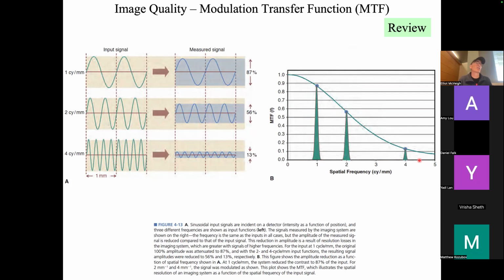You can take that home and compare two scanners: which one's better? You get that 10% value and compare it, and if it goes farther out, that scanner has higher resolution, right? They don't usually give you the details of this whole function, just where it disappears. Sometimes they say 1% so they can make it a bigger number, right?